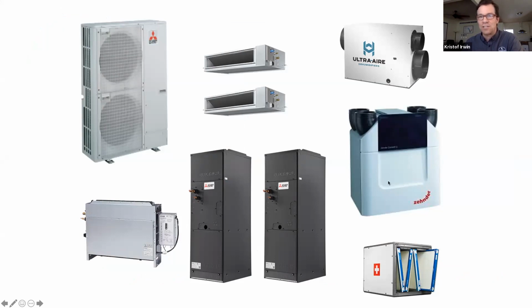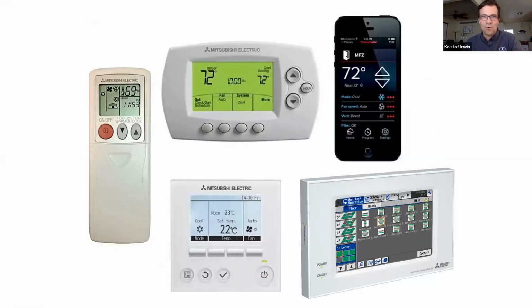ERVs are a huge no-brainer, but for anyone in a humid climate, first you have a dedicated dehumidifier. You have to have a guaranteed dry, cool air mass or your ERV won't work. The motive force for your ERV is the dry, cool air mass itself. And filtration is, of course, doing nothing but getting more important.